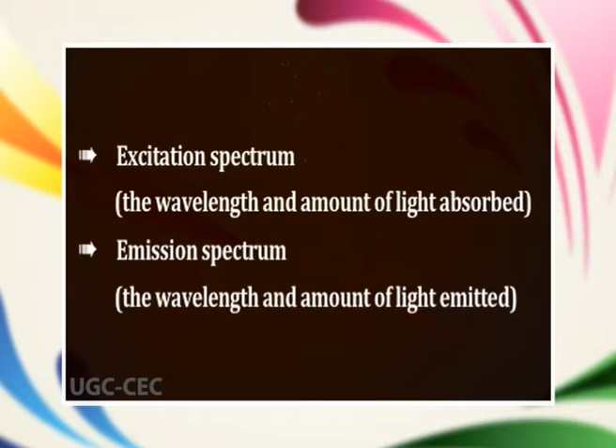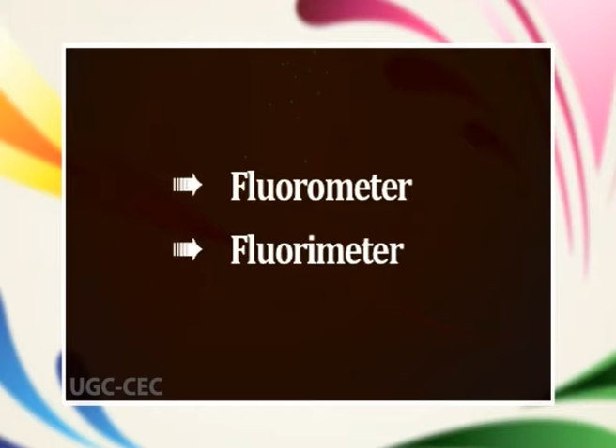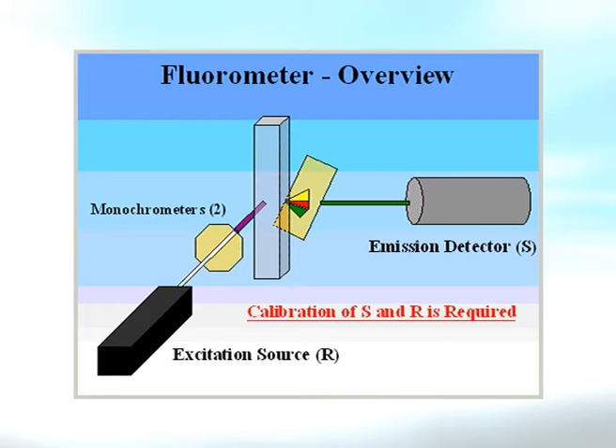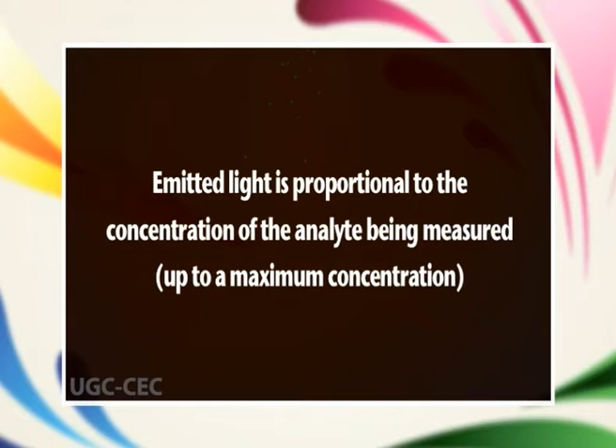Fluorometry is the measurement of fluorescence. The instrument used to measure fluorescence is called a fluorometer or a fluorimeter. A fluorometer generates the wavelength of light required to excite the analyte of interest. It selectively transmits the wavelength of light emitted, then measures the intensity of the emitted light. The emitted light is proportional to the concentration of the analyte being measured, up to a maximum concentration.